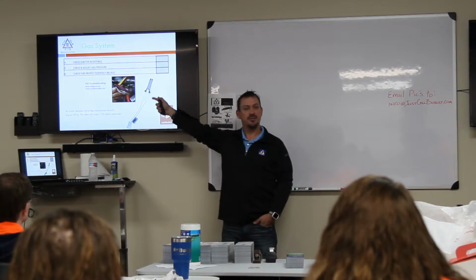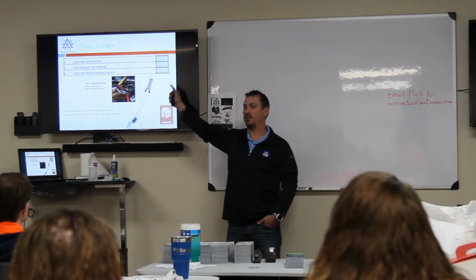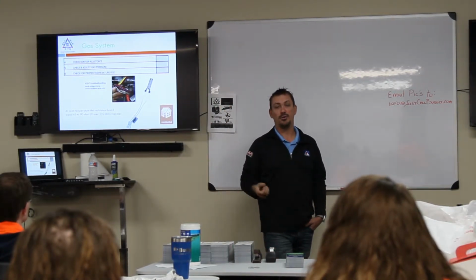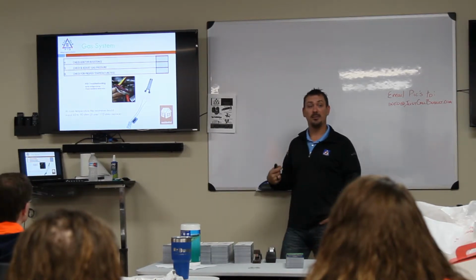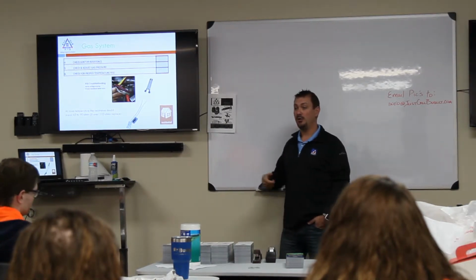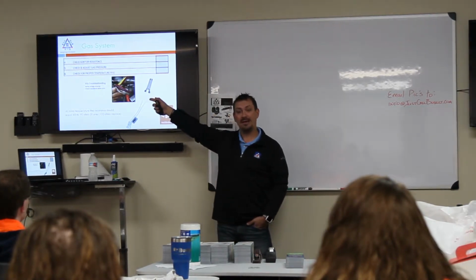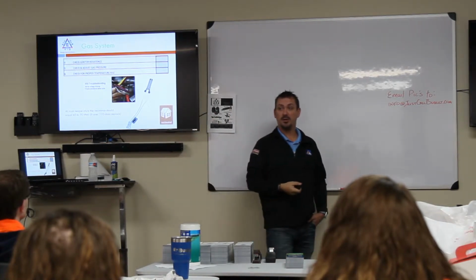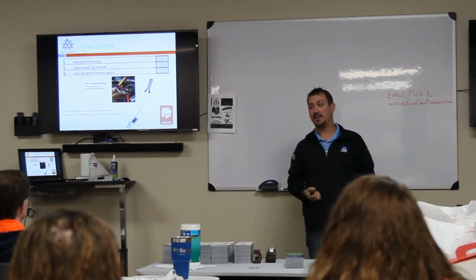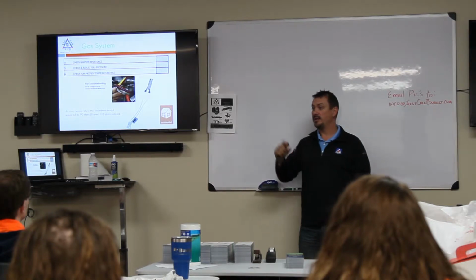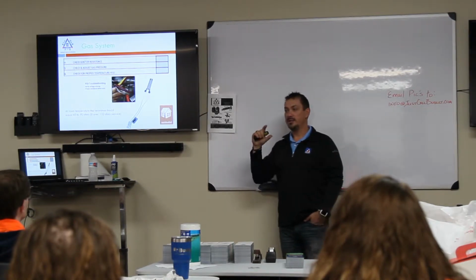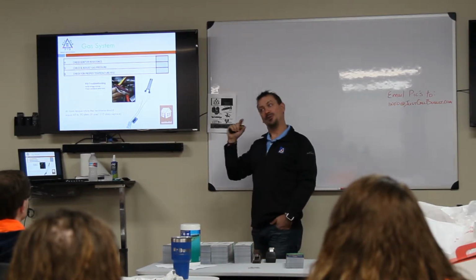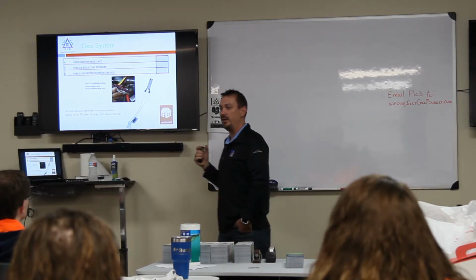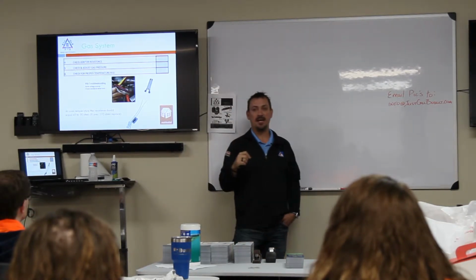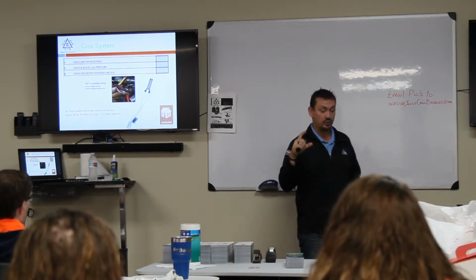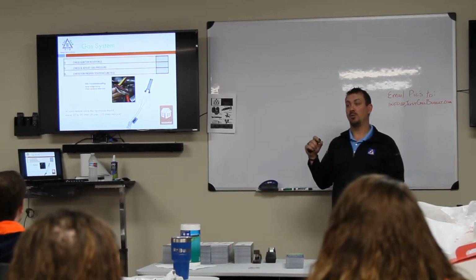Most manufacturers these days are now putting silicon nitride igniters in there, which are a lot more durable, a lot sturdier. I highly recommend, anytime you come upon one of these that is bad, to replace it with a silicon nitride igniter. My favorite is the Hot Rod by White Rodgers. It's a lot more versatile. It's a little bit longer. Sometimes the longer one does come into play, and it won't work on some of the 90% efficient furnaces. They're too long, but they also make a shorter one.